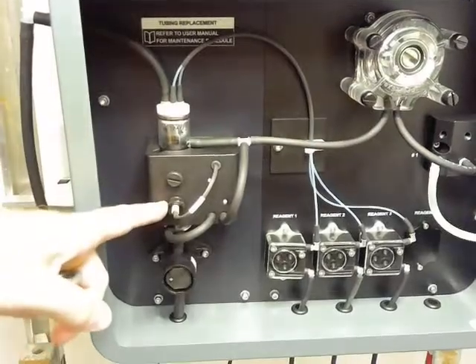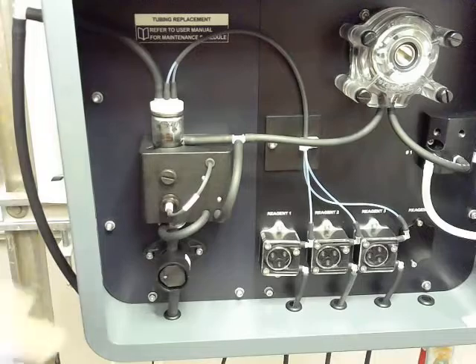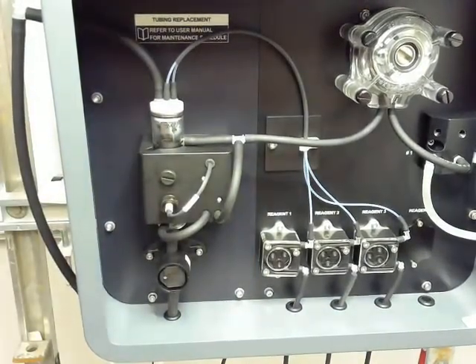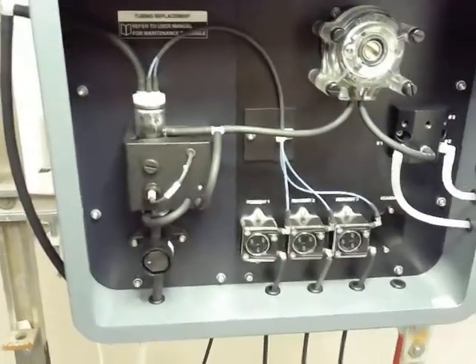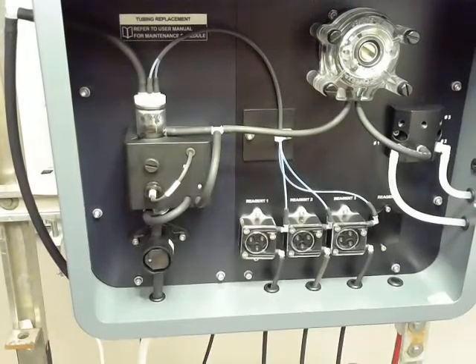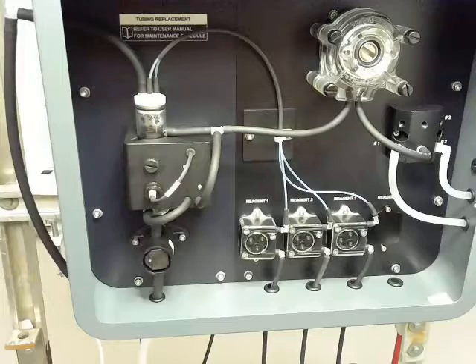Here we have our LED, and again, just our mixing loop. After we run a cal, I'll pull this off just so you can see the mixing pump and the LED and the detector board and what they look like, should we have to get access to them. So basically right now I'll go through your startup procedures in terms of installing your reagents, priming the lines, and then we'll run a calibration. This will be the same process if you're starting from scratch, or doing your monthly reagent replacements, or coming out of an extended shutdown period.